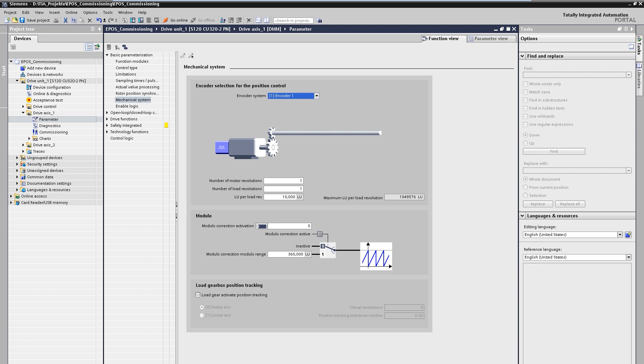Common applications for linear movements for example are realized using spindles whose pitch could have a value of 10 mm per revolution. The preset values would fit this mechanics without gearbox with the position resolution in micrometers.